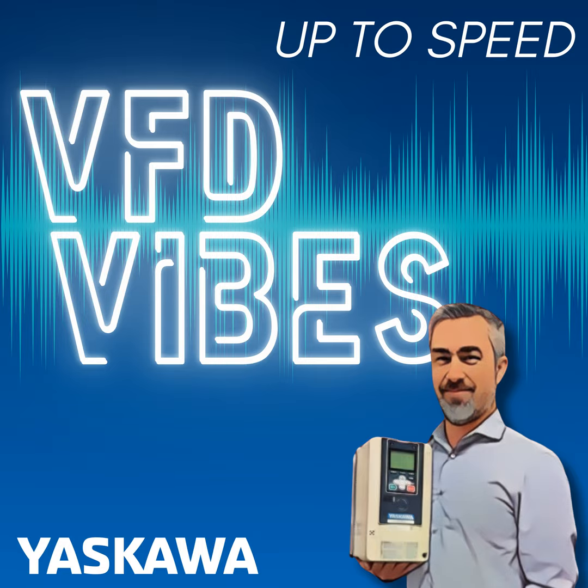Now, we have this neutral here. Typically, the neutral is grounded at the service entrance, almost always connected to ground at the service entrance of the building. It's either connected to ground directly through a wire or through some intentional resistance. So similar to our house setup once again. Exactly. The Y-connected configuration with the solidly grounded neutral is the most common three-phase power configuration.